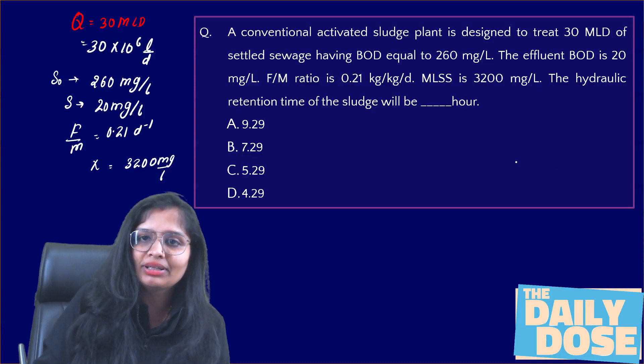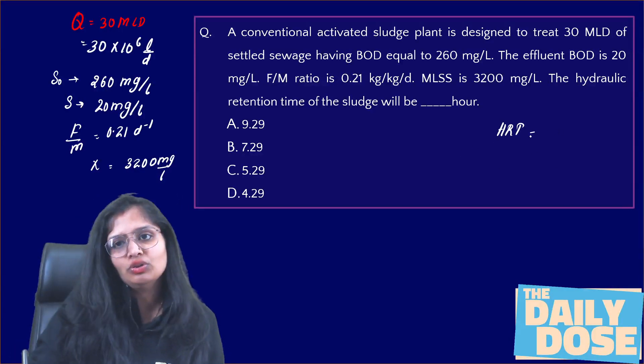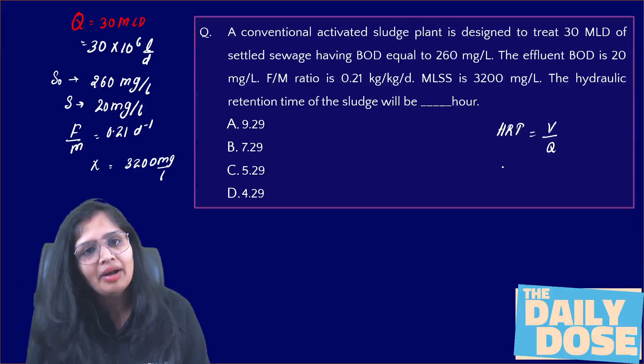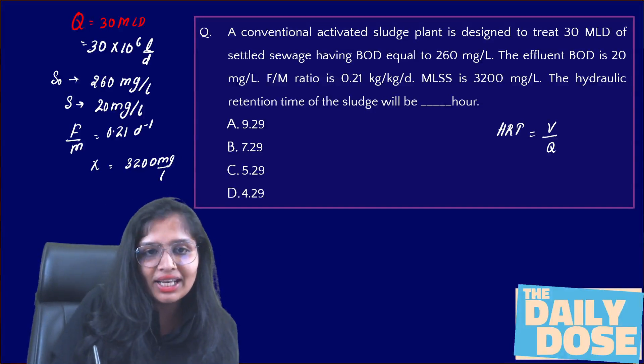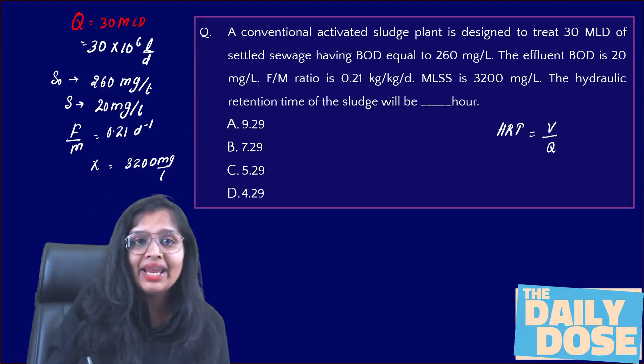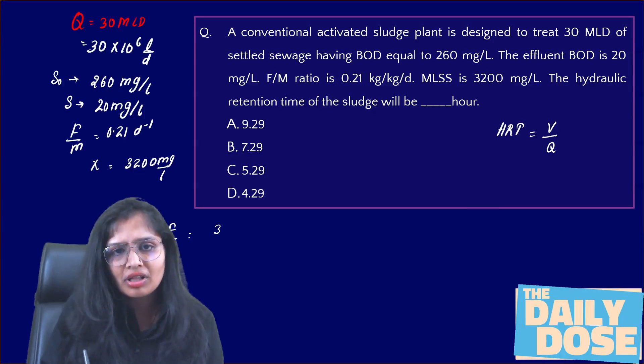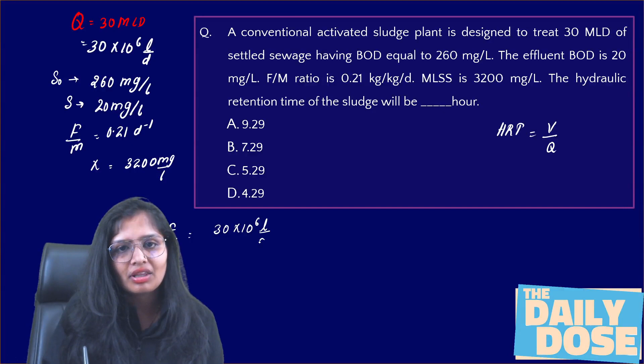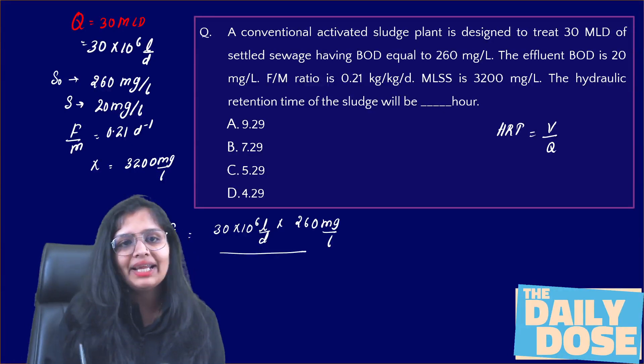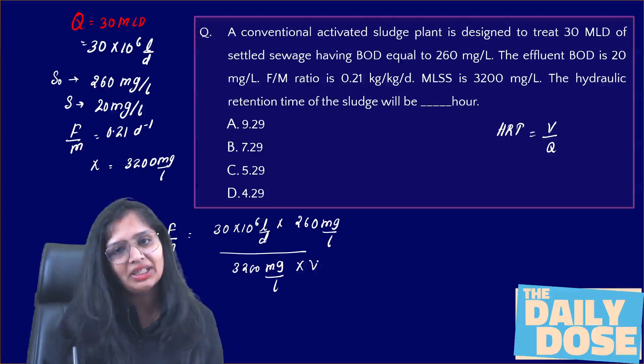Let's write HRT for short. HRT equals volume divided by discharge. Now, volume is not directly given in the question, so we need to find it. We start from the food-to-microorganism ratio. The food is the organic matter: in one litre there is 260 mg of BOD, so in 30 MLD the total food is 30 × 10⁶ × 260 mg/L. The microorganisms are 3200 mg/L in the volume of the aeration tank.